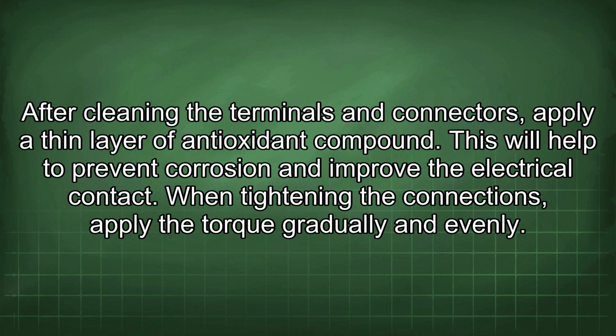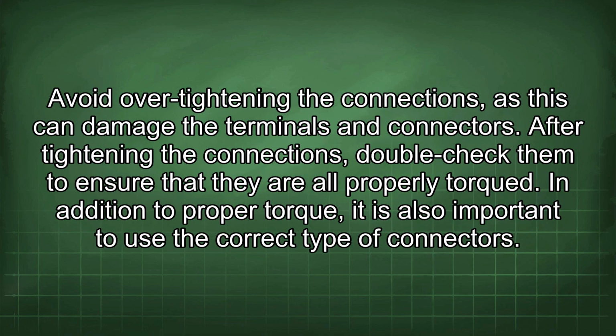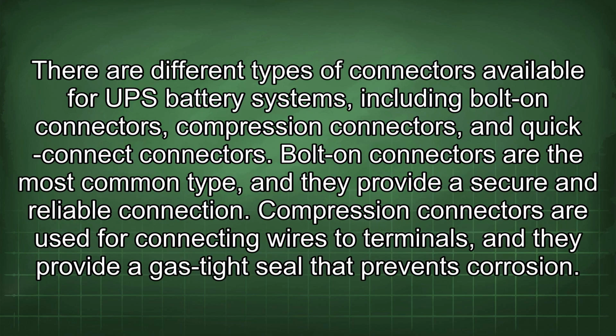When tightening the connections, apply the torque gradually and evenly. Avoid over-tightening the connections, as this can damage the terminals and connectors. After tightening the connections, double-check them to ensure that they are all properly torqued. In addition to proper torque, it is also important to use the correct type of connectors. There are different types of connectors available for UPS battery systems, including bolt-on connectors, compression connectors, and quick connect connectors.